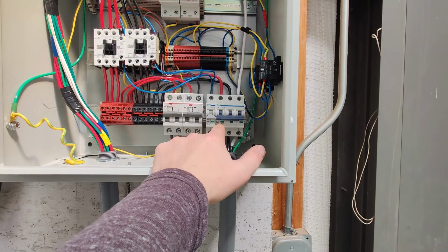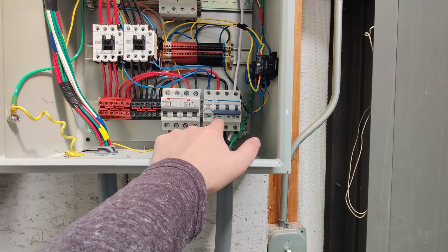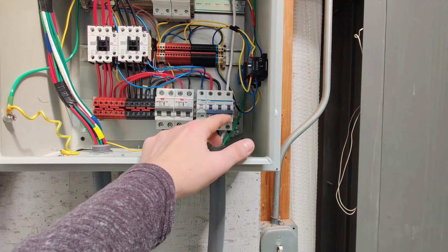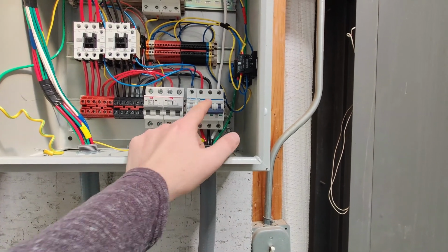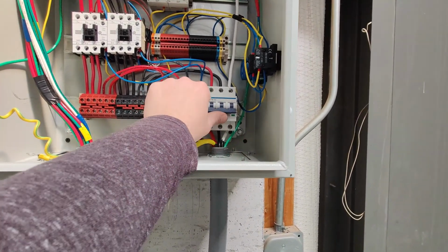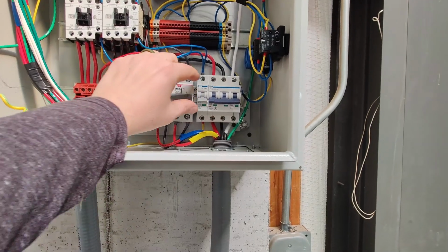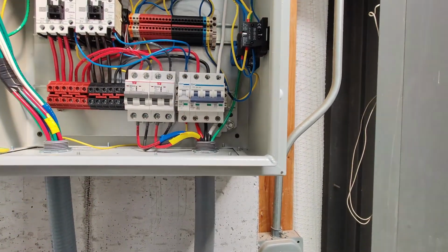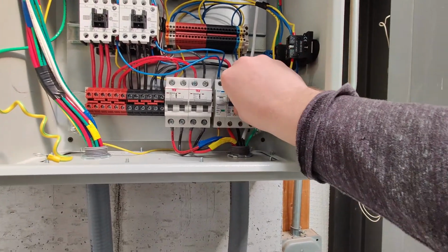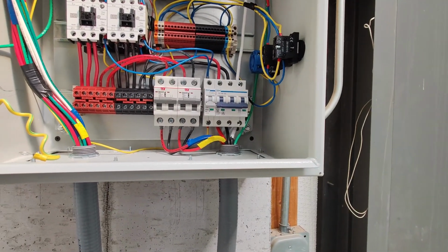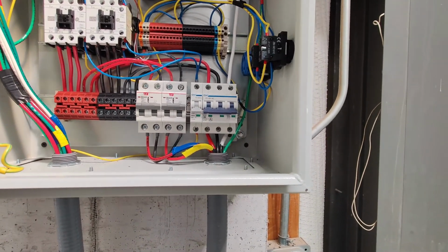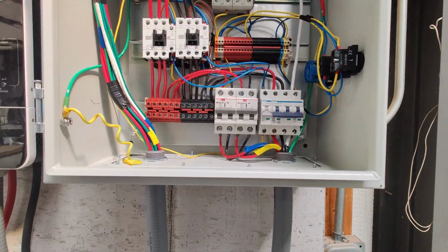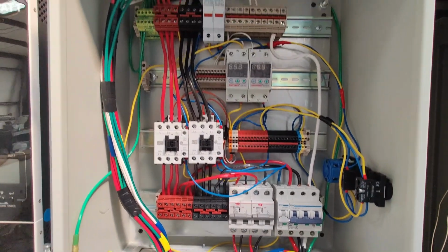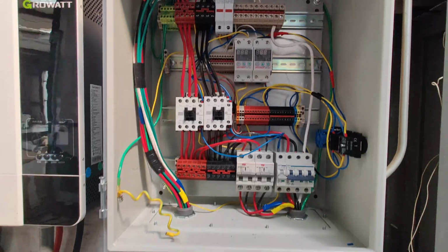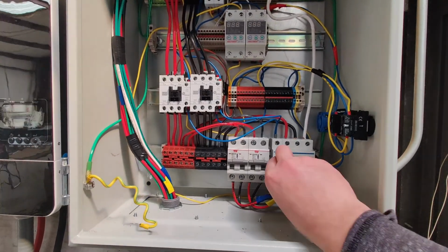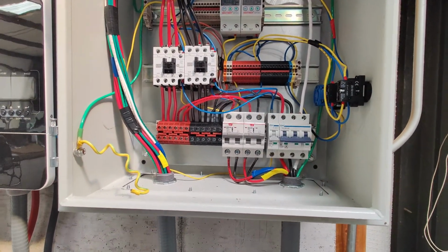The other thing that happened is the shunt trip breaker tripped itself, and the reason I've designed it like this is that we want it to be a one-time reset. If I try to reset this right now, you'll see it just goes right back off, because the contactors aren't engaged. And if the contactors aren't engaged, I should not be able to turn my loads on without the system being in operation. You can see it's all powered down, but I still can't turn that breaker on.